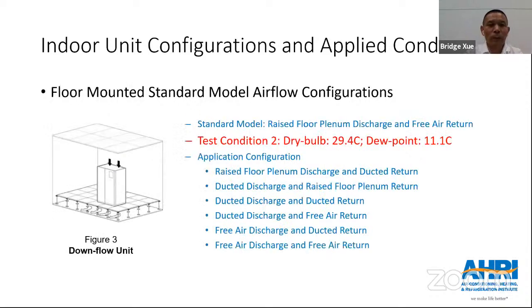Floor mounted standard model airflow configuration: the standard model will be a raised floor plenum discharge and a free air return. The condition will be different because they will be applied in different rooms. The dry bulb will be 29.4 and the dew point is the same. Then you can see the other six different application configurations based on the room design, for example, ducted discharge and ducted return, or maybe free air discharge and ducted return, something like that.